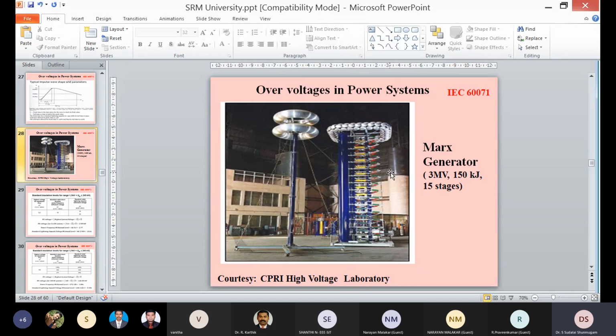Most of the time, if the generator is capable of doing that, we prefer to use the same generator to generate lightning impulse voltage as well as switching impulse voltage. However, recently the limitation in the tolerance value has been removed by the standard, so if you go to many R&D centers, most of them will have a switching impulse generator within them. They only go outside to have lightning impulse withstand voltage tested. The problem is with respect to clearance.